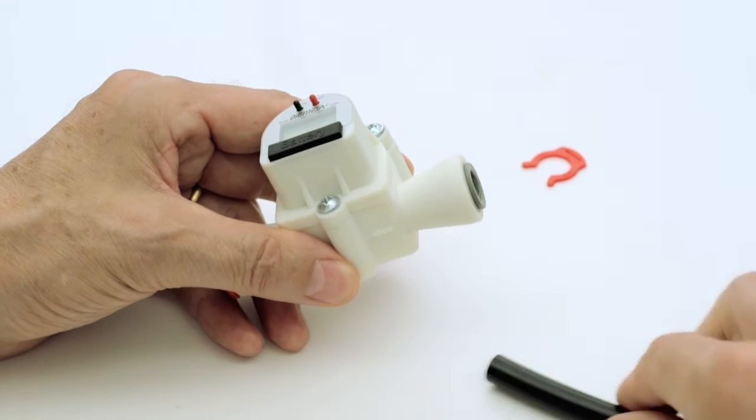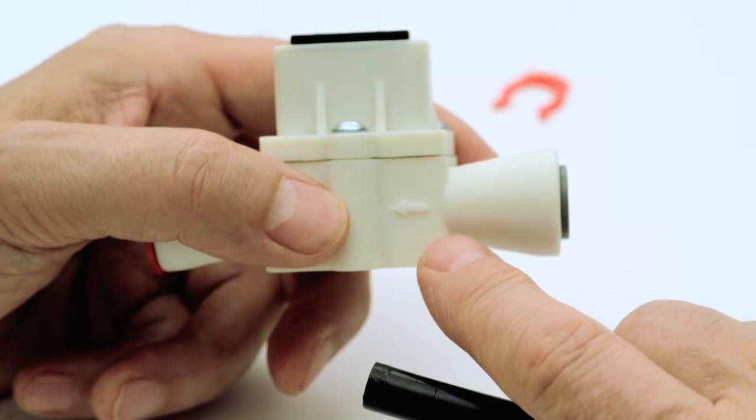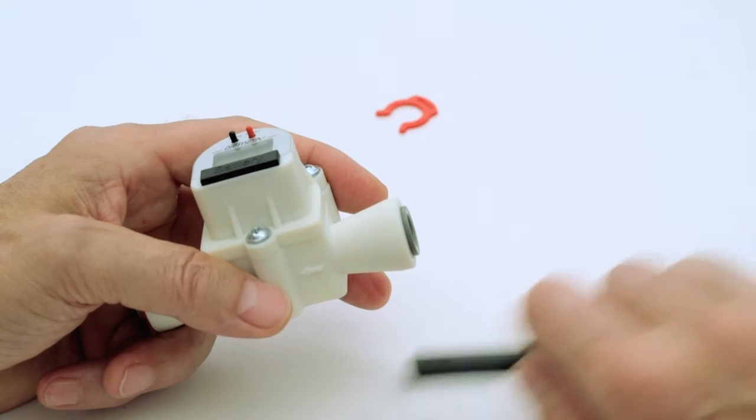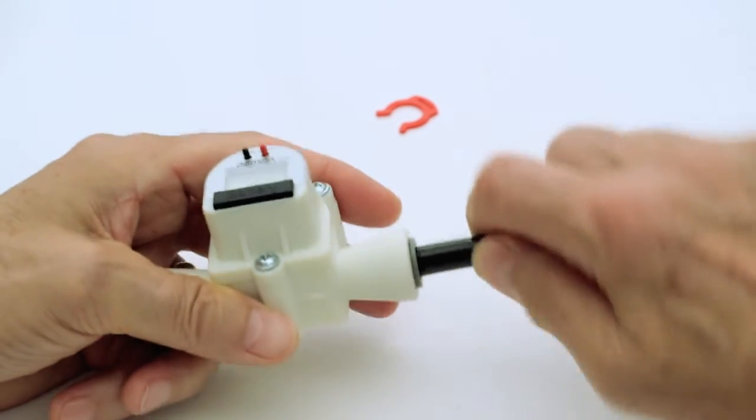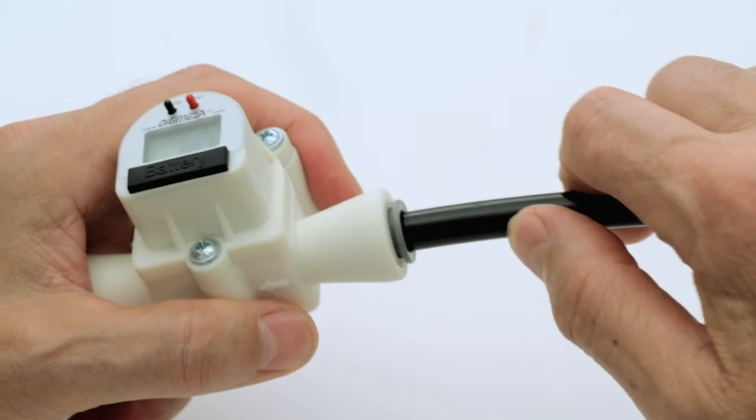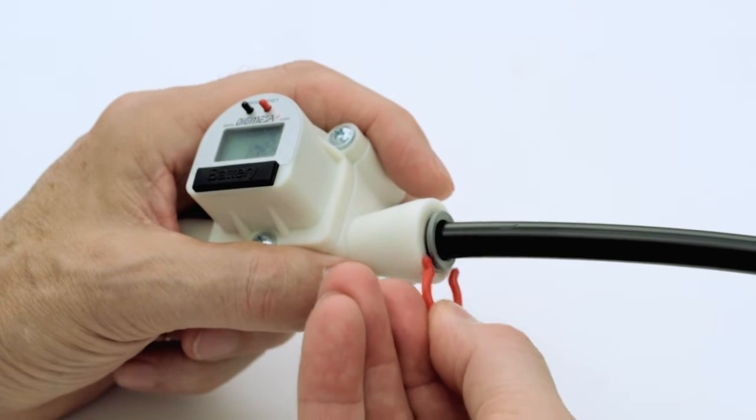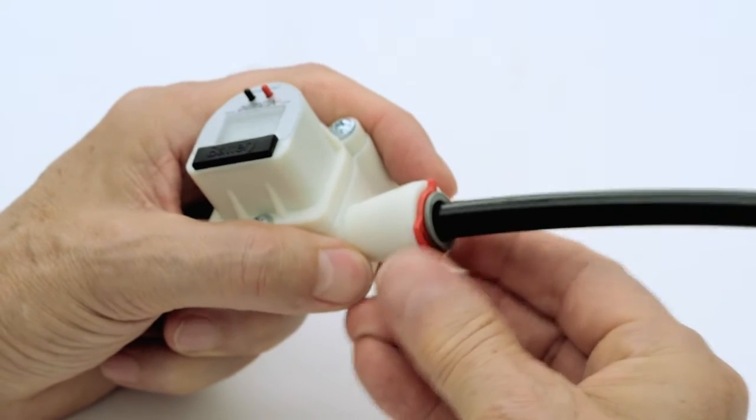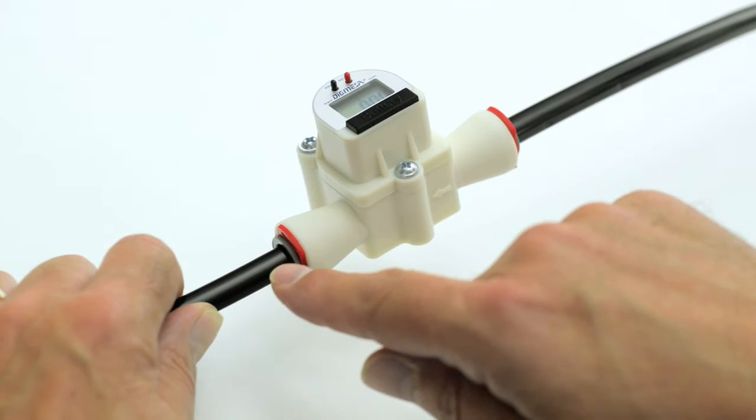Remove the red locking clip. In direction of flow, push the incoming hose end into the flow sensor nozzle inlet until it reaches the stop. To check that the hose is properly anchored, pull it in the opposite direction. Fit the locking clip. Repeat the procedure for the second connection.